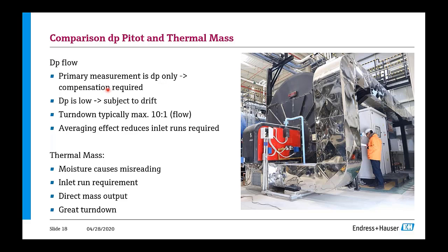With DP flow, the primary measurement is DP only, so you need compensation by pressure and temperature. And they're subject to drift, and their turn down is really low. Typically, you find only a turn down of 3 to 10 to 1 as opposed to 100 to 1 using thermal mass. The averaging effect, however, reduces the inlet runs required.